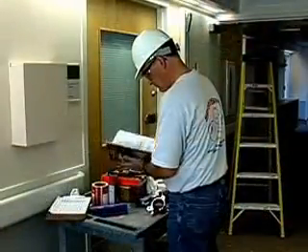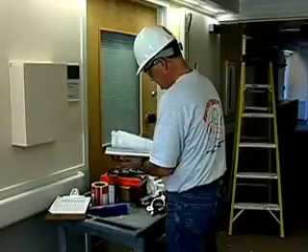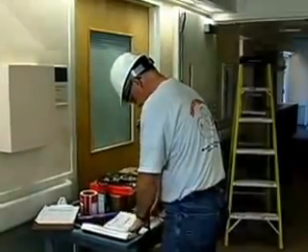If the installation is to be code compliant, an as-built condition must be Firestopped in one of 3 ways. Either choose a Firestop system that has coverage for your condition, or alter your as-built condition until it conforms to the requirements of a tested system. Or, in the case of unusual penetrations, you can contact the manufacturer and request an engineering judgment. The point is that no Firestop should ever be installed without a UL system or an engineering judgment to defend your work. And even then, great care is needed to ensure that the installation matches the system requirements precisely.